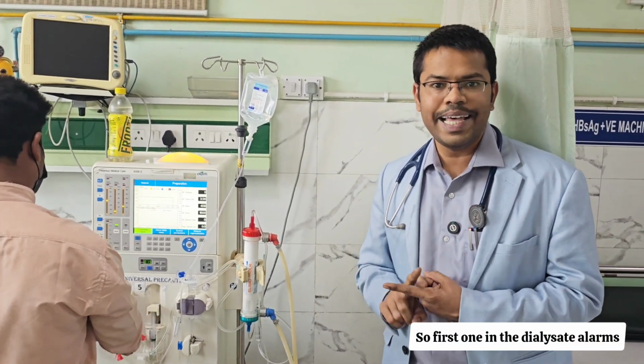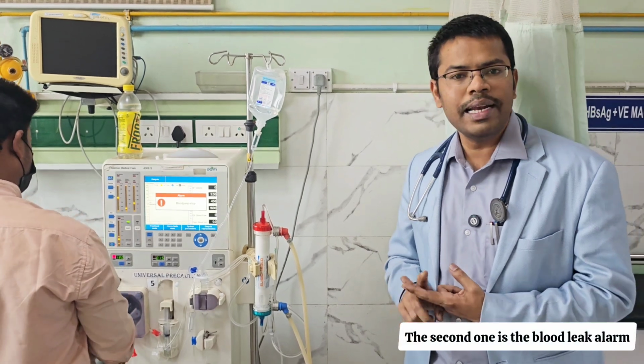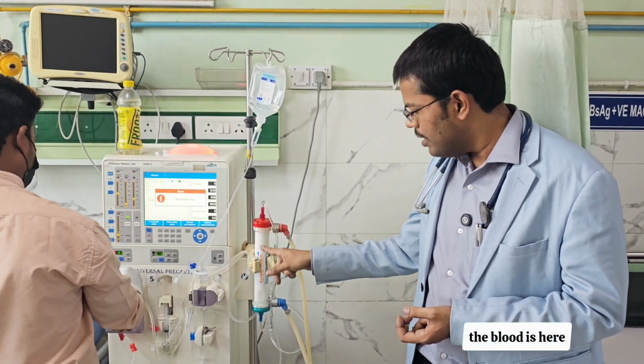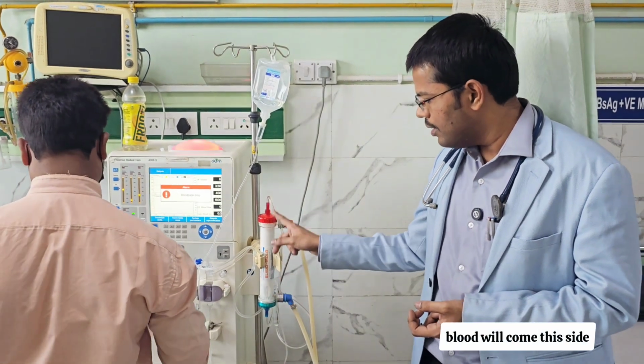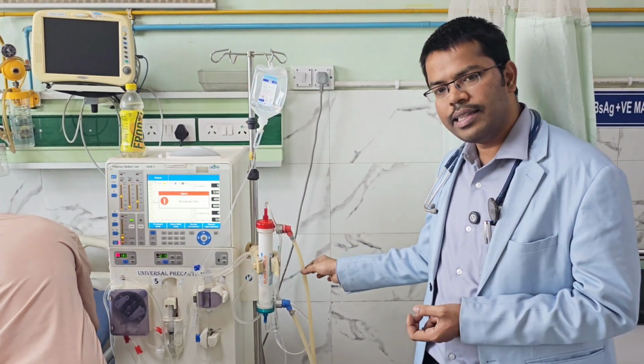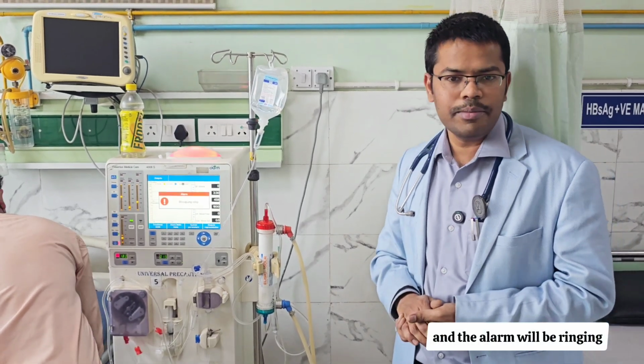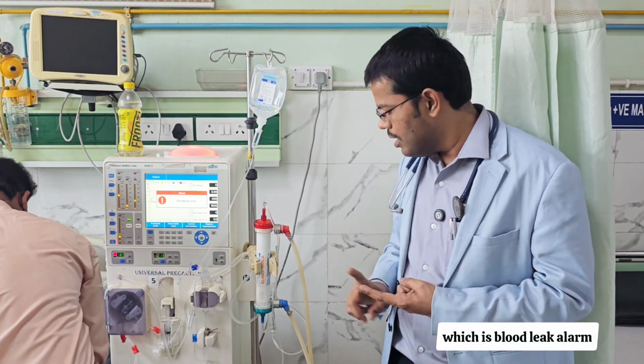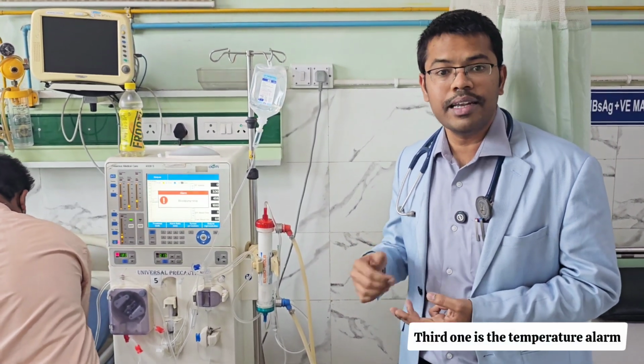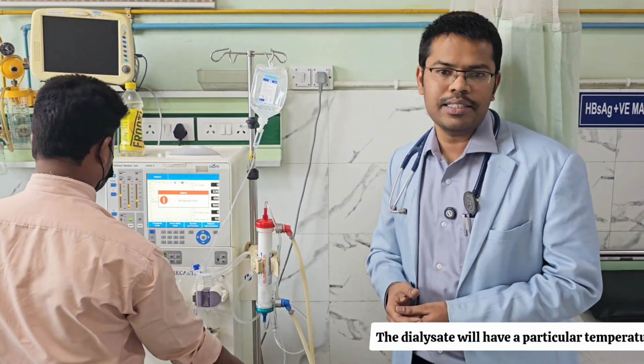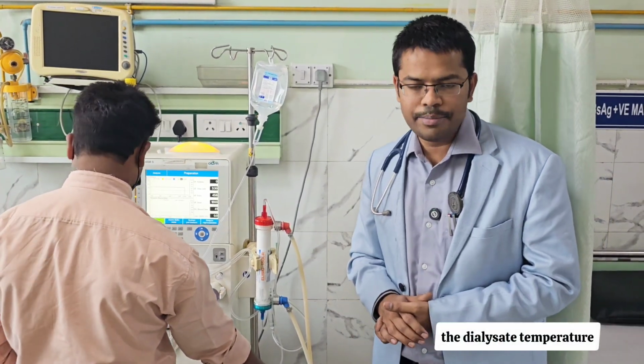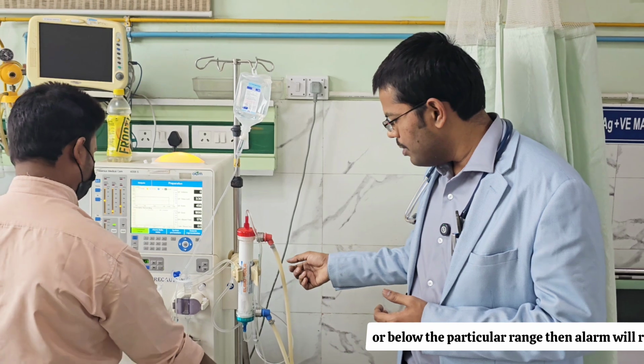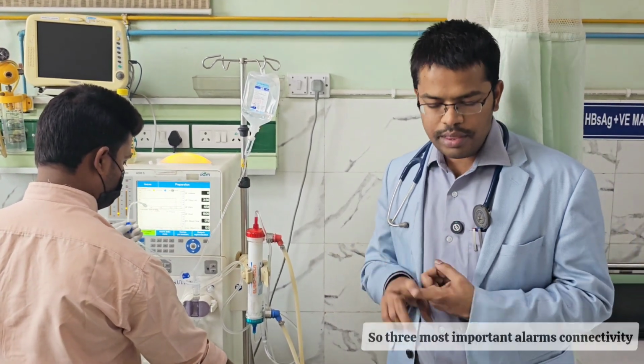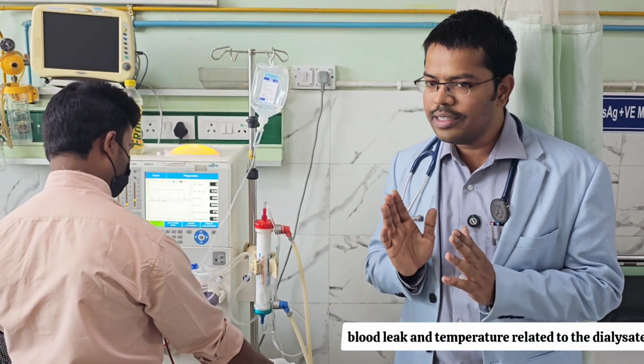So that is the first one in the dialysate alarms. The second one is the blood leak alarm. This is the dialysate side, the blood is here, and when we start the machine, blood will come this side. If blood leaks from this side to the dialysate side, the machine will detect it and the alarm will ring. This is the blood leak alarm. The third one is the temperature alarm. The dialysate will have a particular temperature, and there is already a video regarding the dialysate temperature. When the dialysate temperature goes above or below the particular range, the alarm will ring. So the three most important alarms related to the dialysate circuit are conductivity, blood leak and temperature.